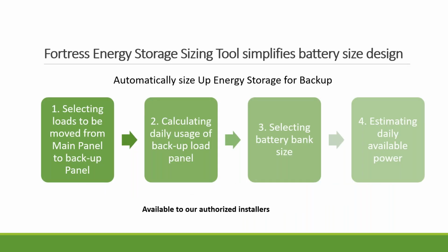Now, a quick touch on how to design battery backup systems. Well, I'm sure you are very familiar with designing a PV system. Once you have that, you're basically going to talk to your clients and figure out what kind of circuits they want to put on the backup panel. You will take those circuits and build up the critical load panel. But again, if your client wishes to back up the whole building, it's doable. It's just very costly. Then based on those circuits you selected, you can look up the total daily consumption. Most clients want maybe 1 day of autonomy, so you can select a battery bank. And if they want longer duration, then you can add more battery banks to it.